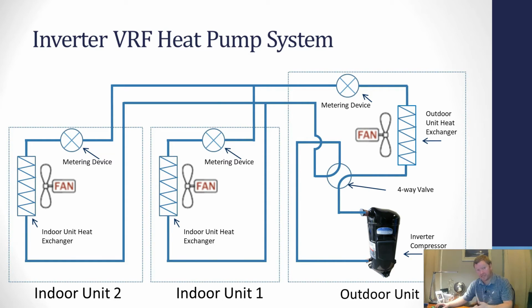Now that PID logic is going to kick in, and the compressor is going to see that you only need 1 degree. So it's not going to ramp up. It's going to run very, very low speed. And then it's going to do the same thing for indoor unit 2. Maybe indoor unit 2 wants 71 degrees and the room temperature is 67. There's no offset. It's going to look at that as 4 degrees and it's going to tune to whatever speed it needs to get to.